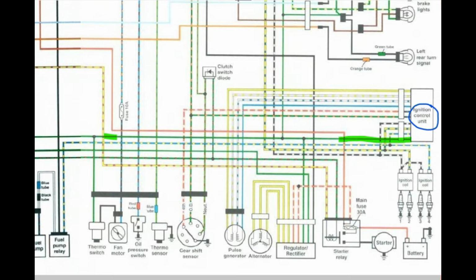Then we move on to that ground line as it comes out of the black box. You test every single other line, and there should be no connection there, so it should read infinity on whatever scale you're using. That means there's no continuity. If there is, that's probably an issue, because I believe the circuits are designed to isolate the ground.